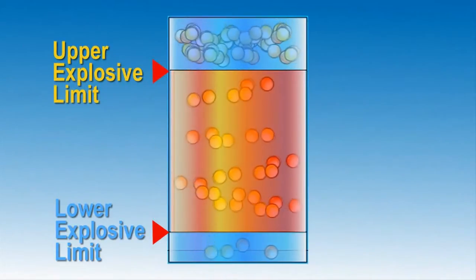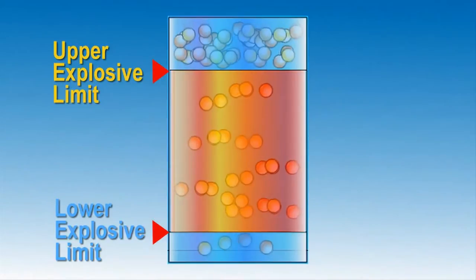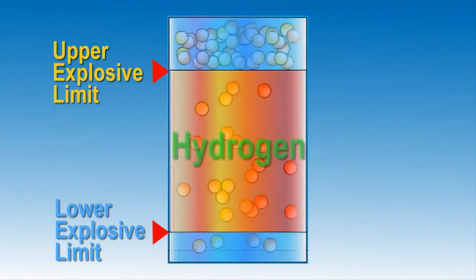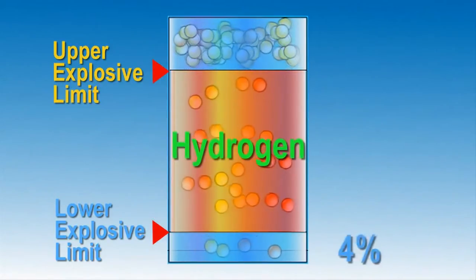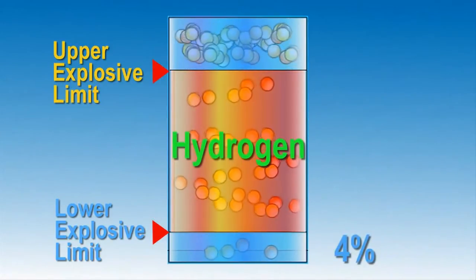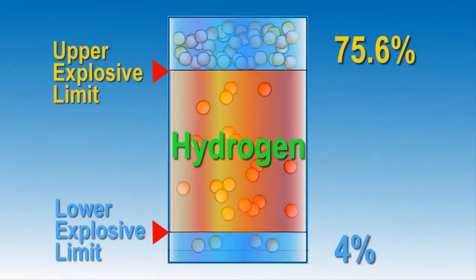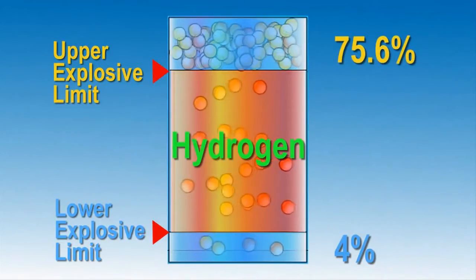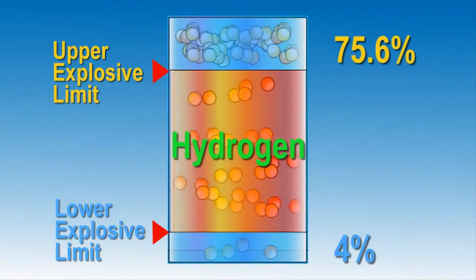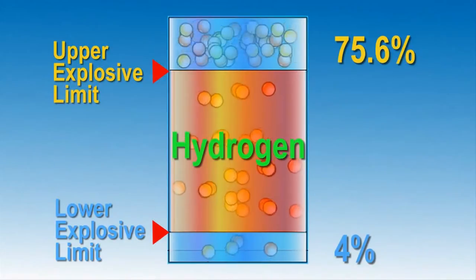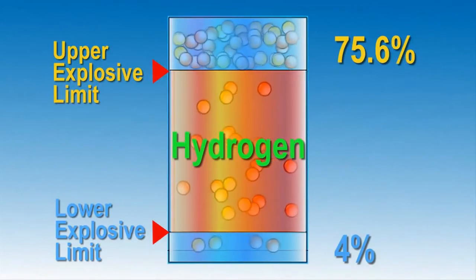It should be noted that different gases will have different threshold limits. In this example, the LEL of hydrogen is 4%, and the UEL is 75.6%. Therefore, any mixture of hydrogen and air that falls between these limits will have a flammable mixture.